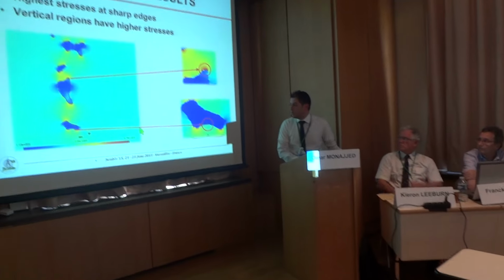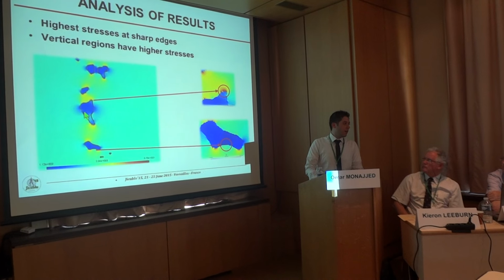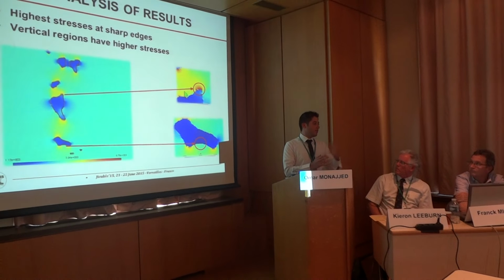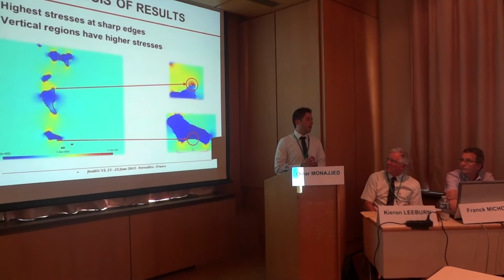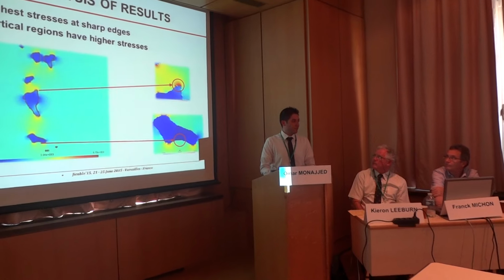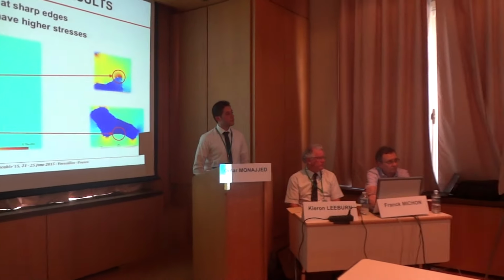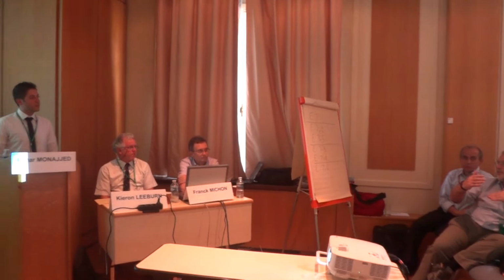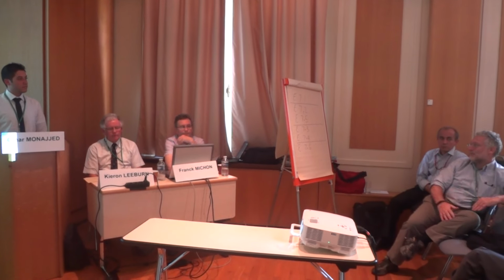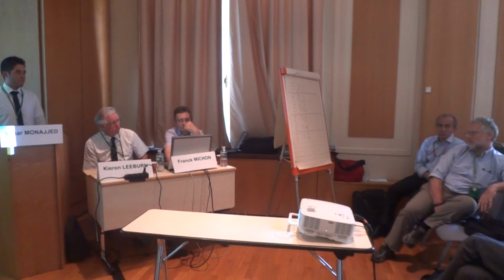Actually, I did not do this, because it was showing you that this is the biggest impurity here, and it has the highest stress. So maybe there's a relation between the size of the impurity and the maximum stress. But I did not perform it. Because 6 kV per millimeter is a big stress if you're looking at it over a couple of millimeters, but that's not a high risk of breakdown if it's on a 100 micron or a 10 micron level. And so that's the trouble of scaling that you have with all of these finite element assessments. Maybe in the future we're...